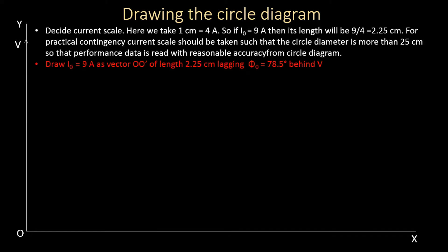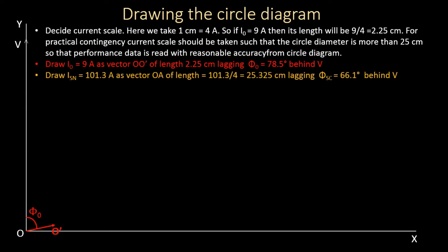We draw I0 as vector OO' from the origin, of length 2.25 centimeters, lagging the voltage by 78.5 degrees. We measure 78.5 degrees from the vertical axis and draw OO'. Next, we draw the normal short-circuit current of 101.3 amperes, named vector OA. Its length is 101.3 divided by 4, which equals 25.325 centimeters, lagging 66 degrees behind the voltage.